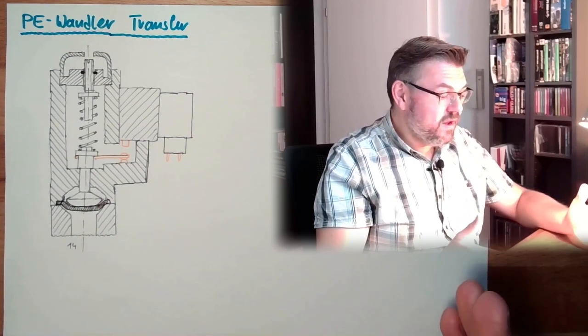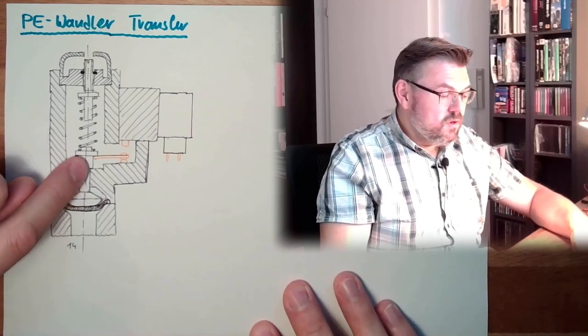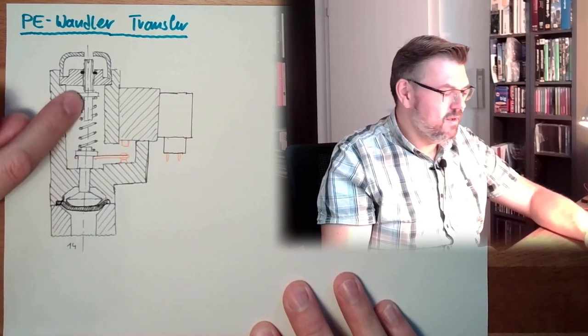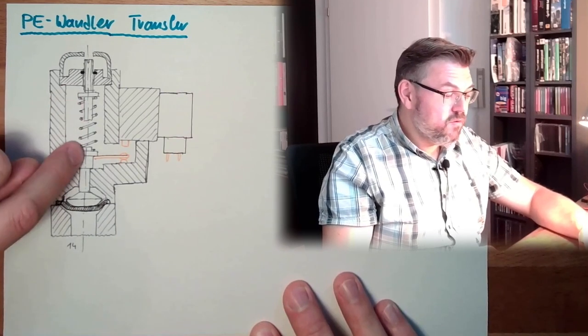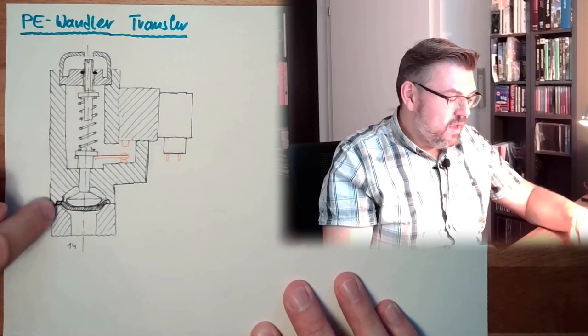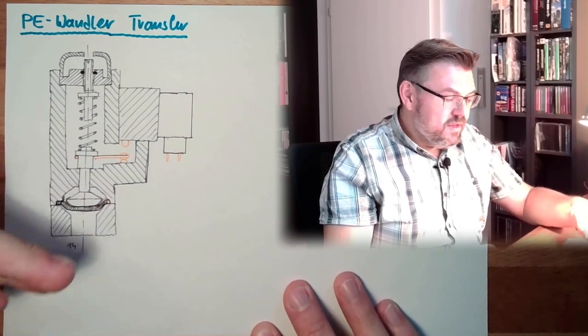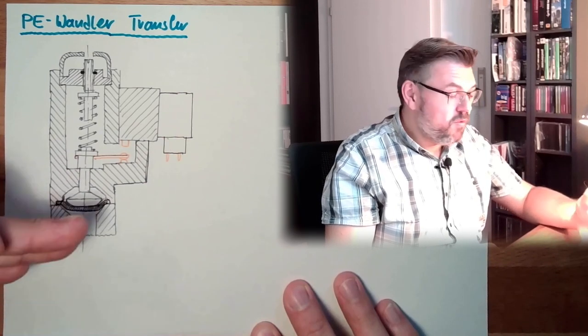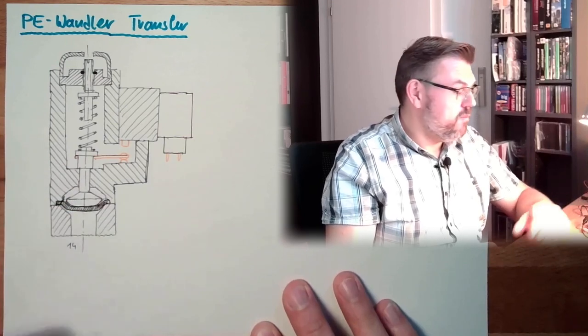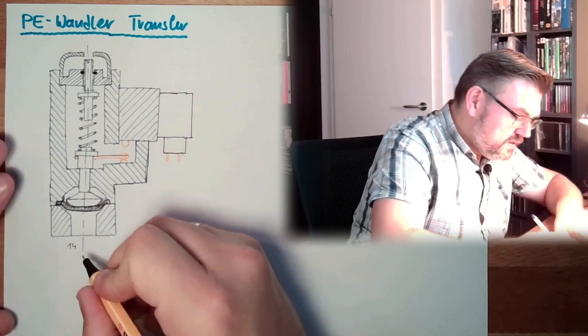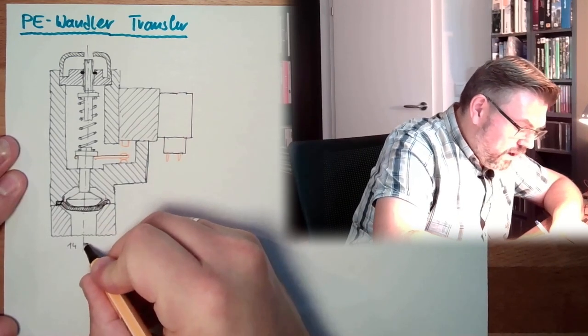What we've got here actually is some rod, which is spring-loaded. Here this shall be a spring, this rod is spring-loaded. And we can adjust the tension of the spring by the help of a screw. And down here we have, in this case it's a pneumatic valve, or pneumatic switch, pneumatically operated switch. Here we have a membrane. And our pressure is coming from this side, here we apply air.